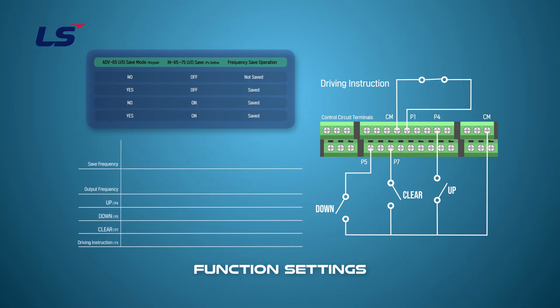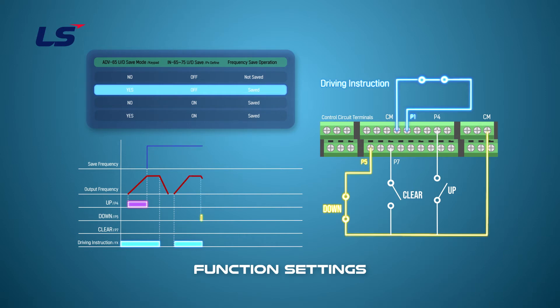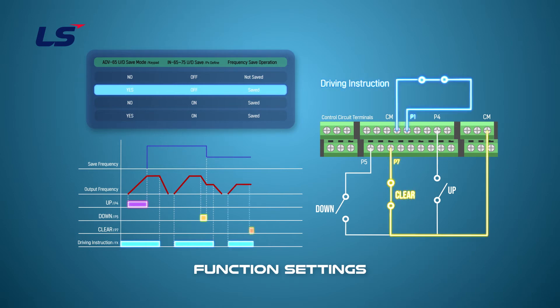The diagram shown on the screen shows when ADV 65 is set to Yes. When the ADV 65 UD save function is set to Yes, the operating frequency during constant speed is saved regardless of the multifunction digital input up-down save input status. To clear the stored frequency, assign one of the multifunction digital inputs to Clear and turn it on.